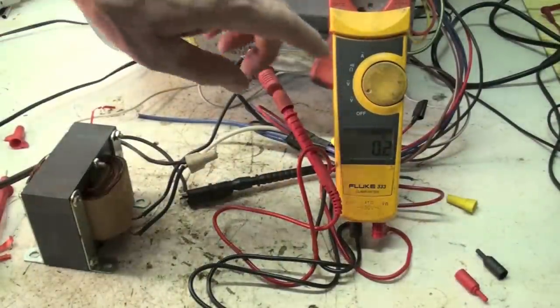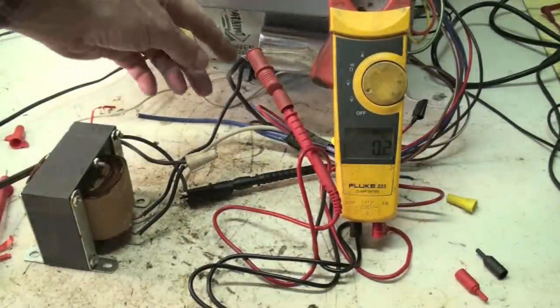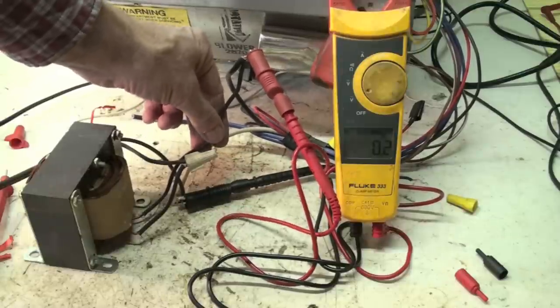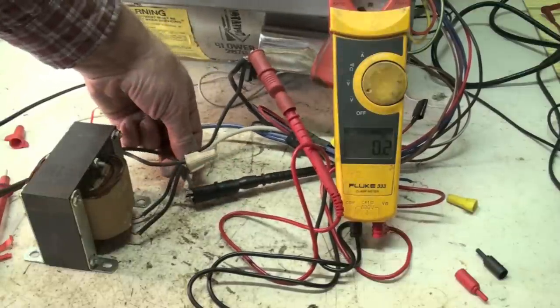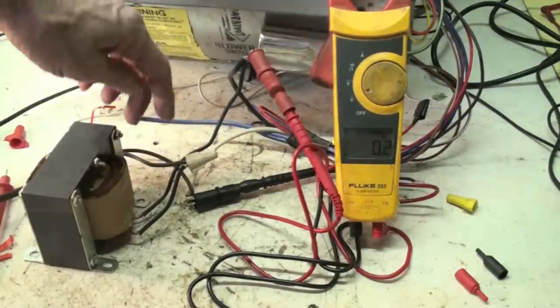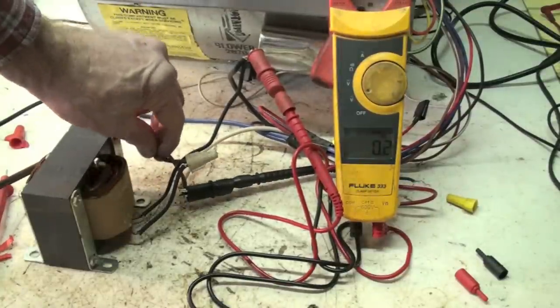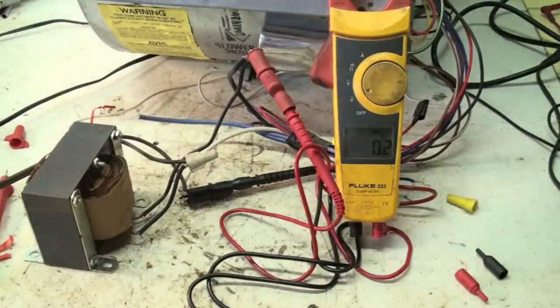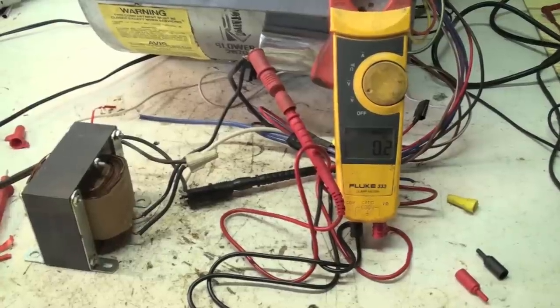I've got the voltmeter hooked up here. This is the lead coming out of the choke coil and I've got another lead hooked to the white. So power coming in is here, coming out of the choke coil is here. Let's see what the voltage is when we start this motor up.